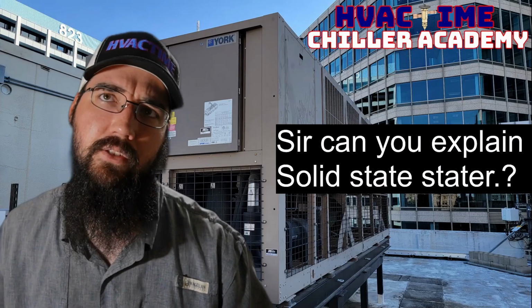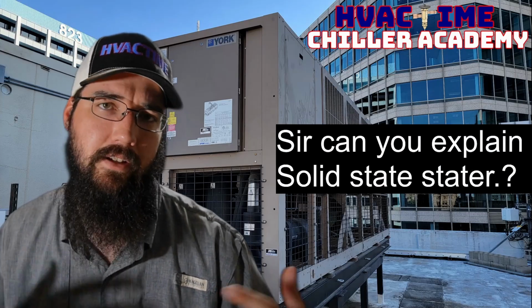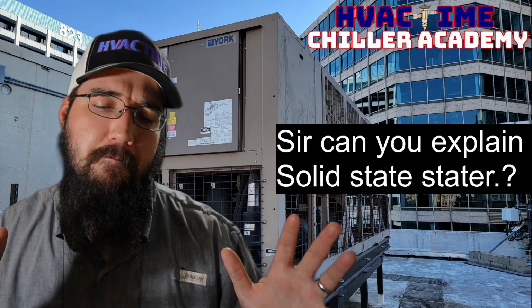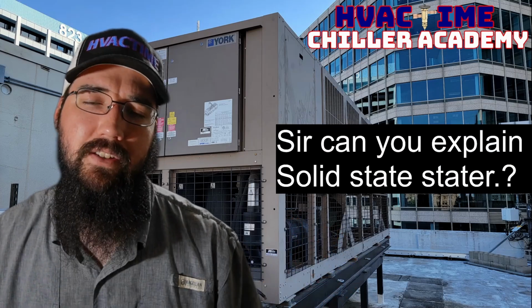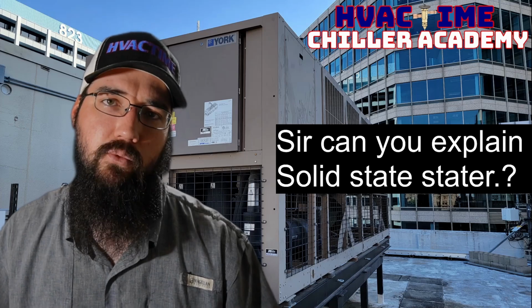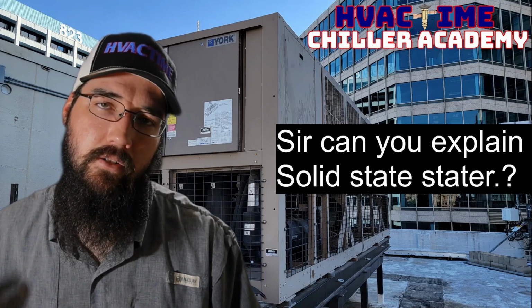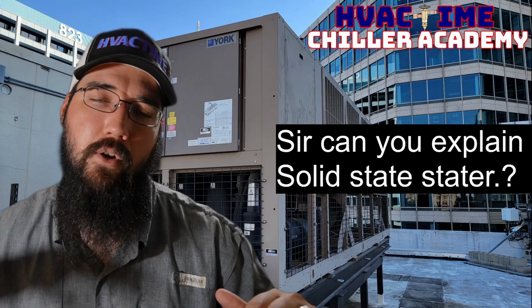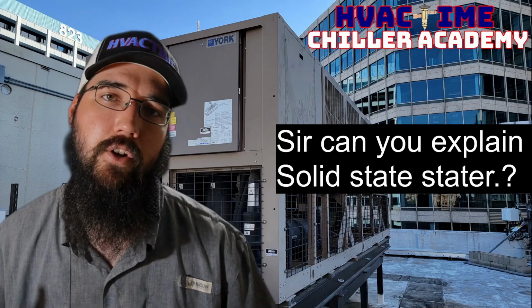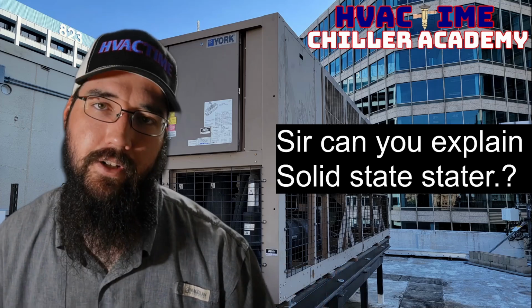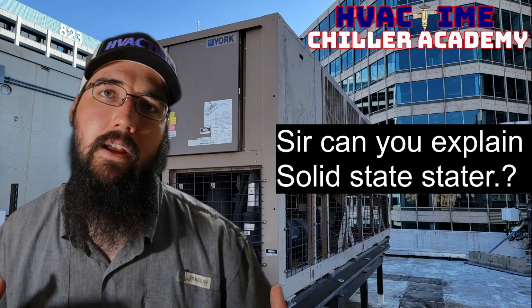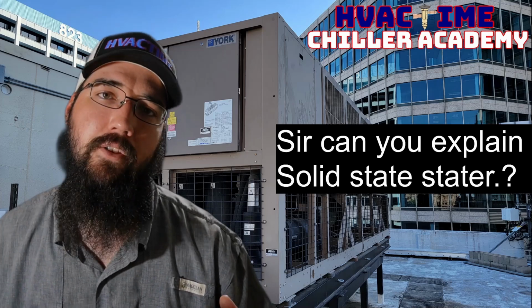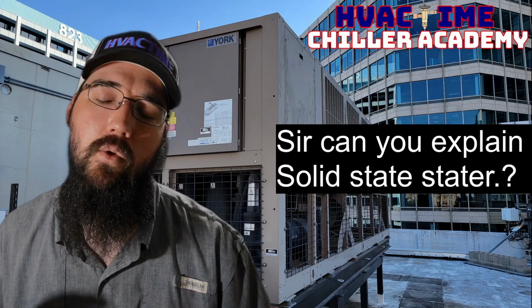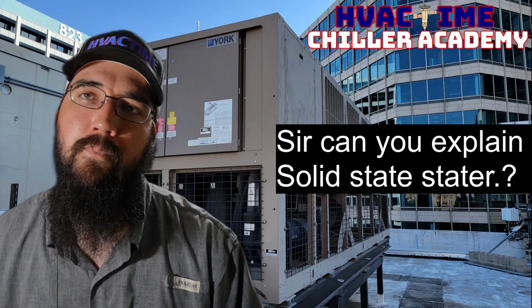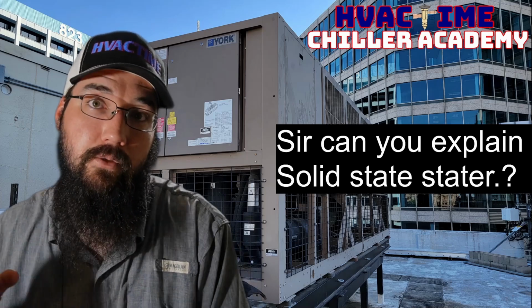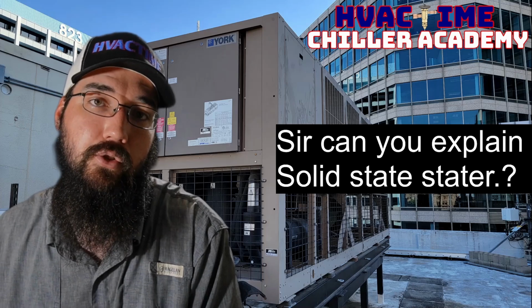Without getting crazy into the electrical schematics next and diving into that aspect of it, that is what a solid state starter is accomplishing. We're flowing through an SCR to slowly ramp the motor to lower the inrush current, so that we save energy and we put less stress on the motor. And then depending on the style, we either transition to an electromechanical, or we have enough cooling on the SCRs to lock it in.